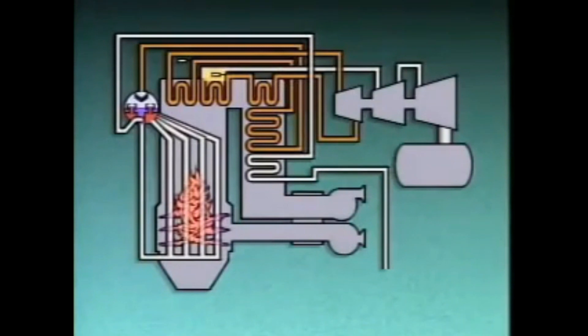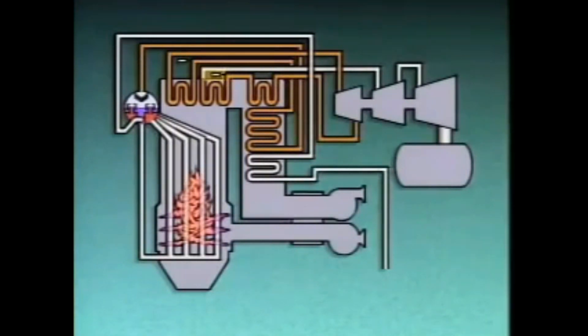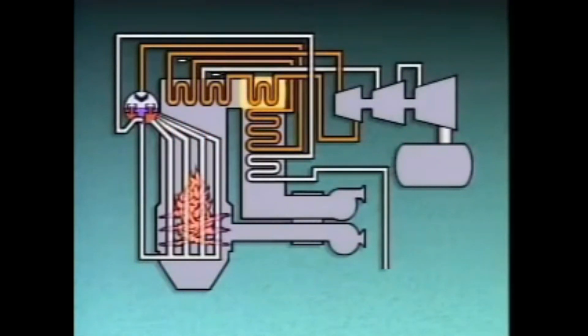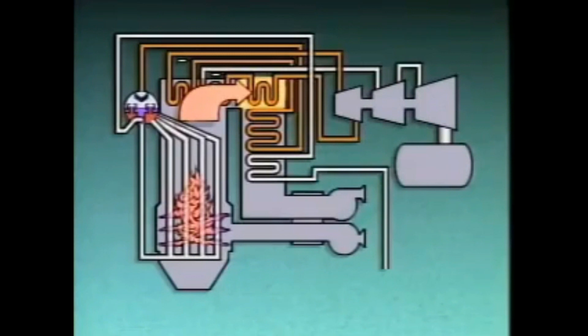An attemperator, located at the beginning of the secondary superheater, is used to control the final temperature of the superheated steam leaving the secondary superheater. The attemperator sprays water into the steam flow if the steam gets too hot. The secondary superheater can be classified as a radiant superheater, because it is located in a line of sight with the boiler flames and receives most of its heat by radiation from the flames. The primary superheater is located farther from the flame, and it receives most of its heat by convection from the hot combustion gases, so it can be classified as a convection superheater.